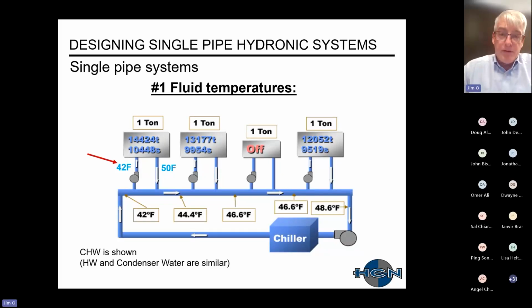So what happens with the fluid temperatures on a single pipe system? Here is a schematic just showing 4 small terminal units. Let's just call them fan coils. It's a cooling system. You have a circulating pump.